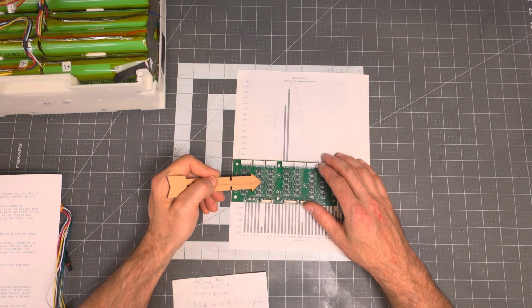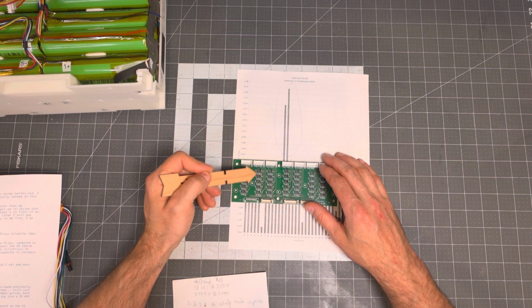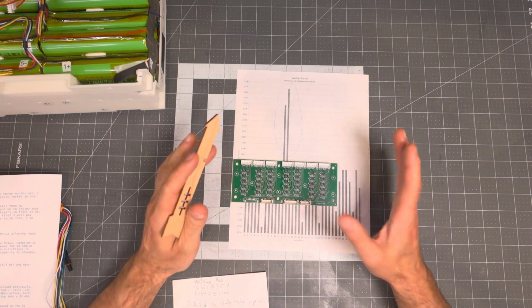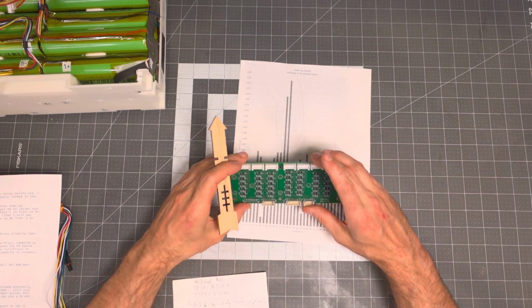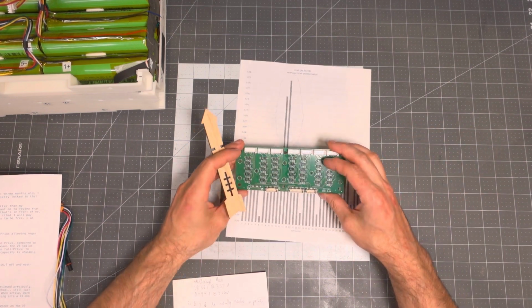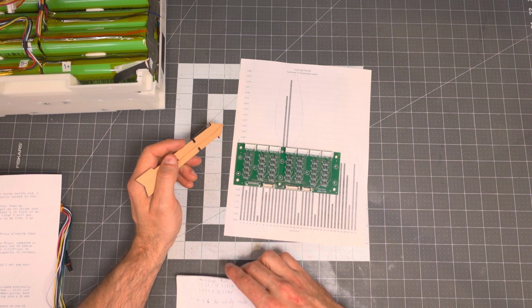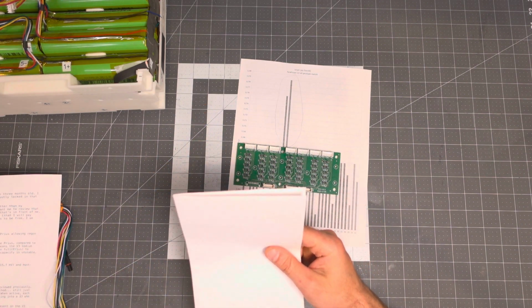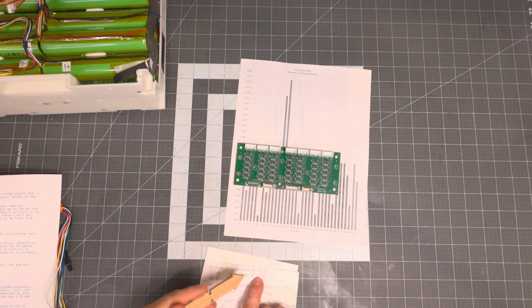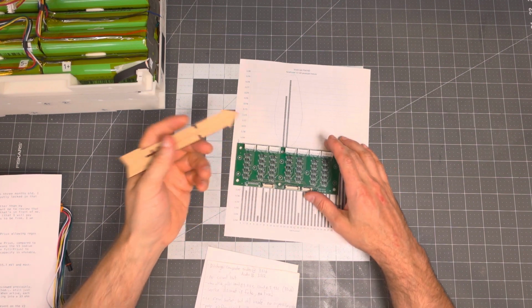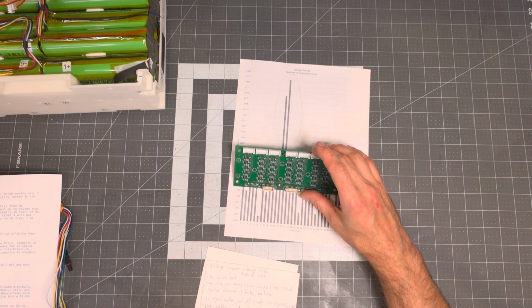There's a case where one cell goes high and the others go low, and you never detect that in the OEM system. This isn't detecting anything like that -- it's literally turning a switch on if the voltage is above 3.516 volts, and back off if it's below. That's the only balancing that can occur.